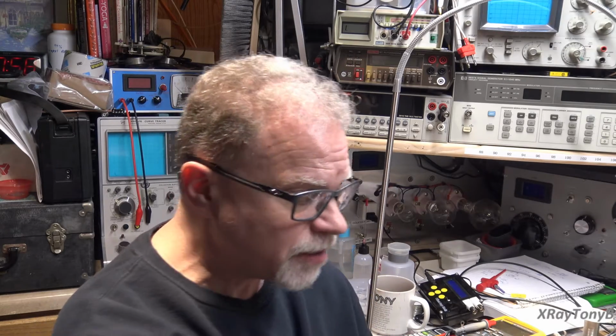So the filaments were running very cool, not at the proper temperature, which causes all kinds of problems with how the tube performs. In addition, the voltage on the high voltage winding was way too high, and I think they kind of offset one another by doing that.